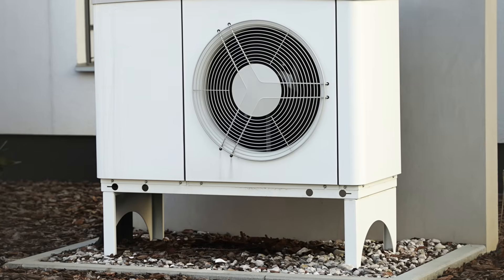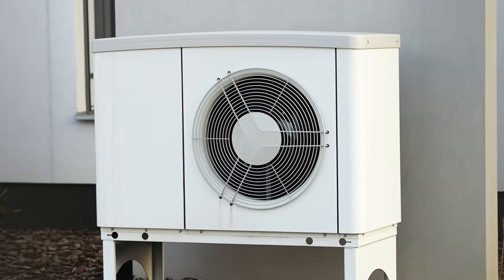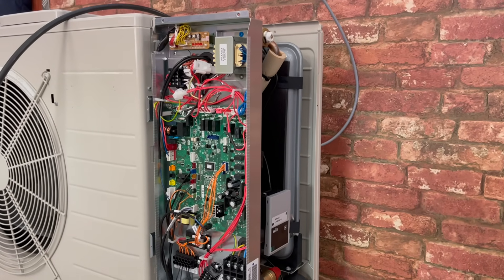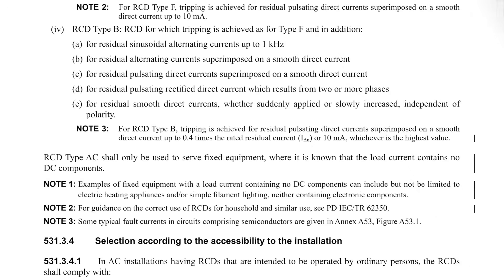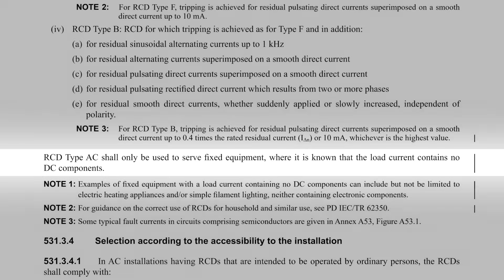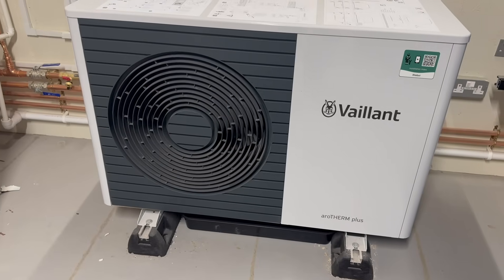But is this all a bit of fuss over nothing? Surely just bunging a type AC RCD in will do the job, right? Wrong! Type AC RCDs aren't sufficient for heat pumps because heat pump systems often produce high-frequency electrical noise and DC components, which type AC RCDs are not designed to detect. And worse than that, the DC electricity that the heat pump may generate can blind the RCD. In fact, Regulation 531.3.3 of Amendment 2 to BS7671 states that RCD type AC shall only be used to serve fixed equipment where it is known that the load current contains no DC components. So that restricts the use of type AC RCDs for any equipment that produces DC components, which includes most heat pumps.